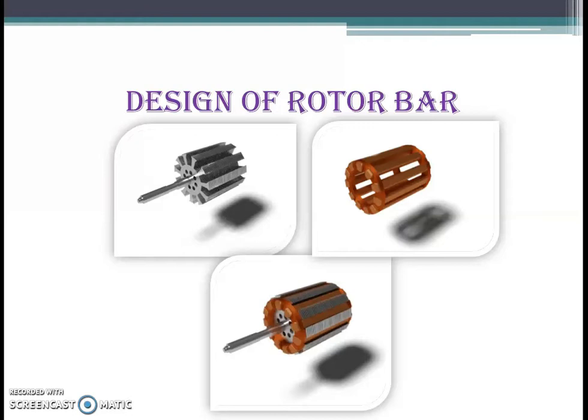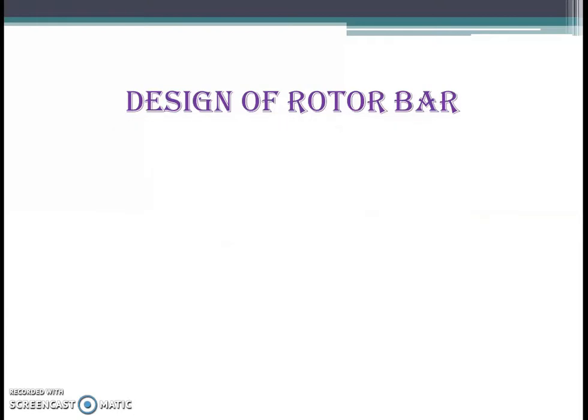In today's lecture, our objective is to decide the rotor bar area as well as the design dimensions of the end ring. The number of rotor bars is exactly equal to the number of rotor slots, as is clear from the figure. The shape of the rotor bar normally takes the shape of the slots. Let us now start the design of rotor bar.